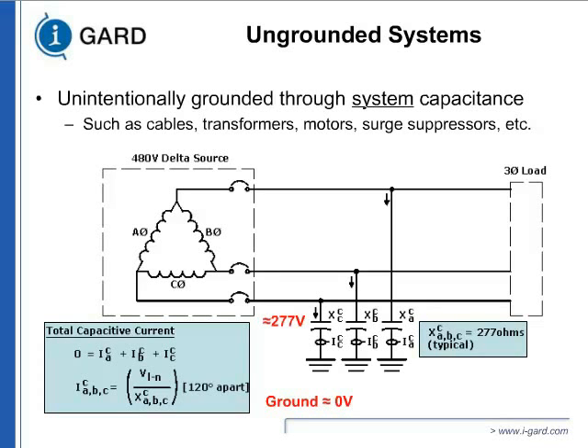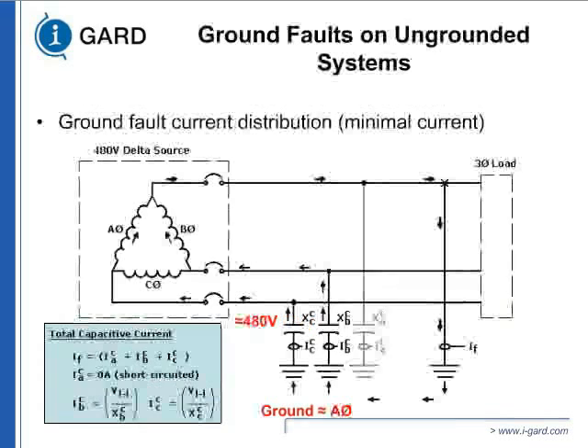When there is a ground fault, the current cannot go back to the system. There is no return path, but it still builds up a voltage to the ground. And you can see when the A phase is grounded, the capacitive coupling will start discharging, and that's where the arcing starts. Ideally, as an electrical engineer, you like to have a bolted fault. A bolted fault is better than an arcing fault. And when the arcing fault happens like this, it shows very minimal current.